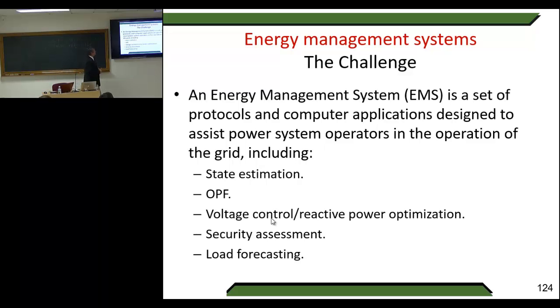What is an energy management system? It's a set of protocols and computer applications designed to assist power system operators in the operation of the grid, including state estimation, optimal power flow, voltage control, reactive power optimization, security assessment, load forecasting. This is the whole package.